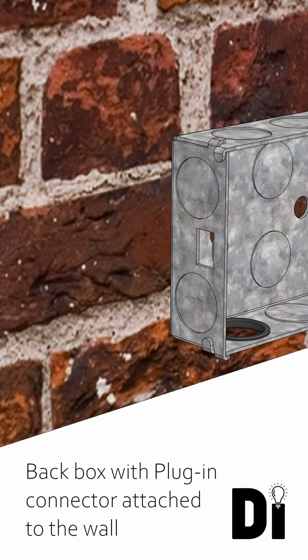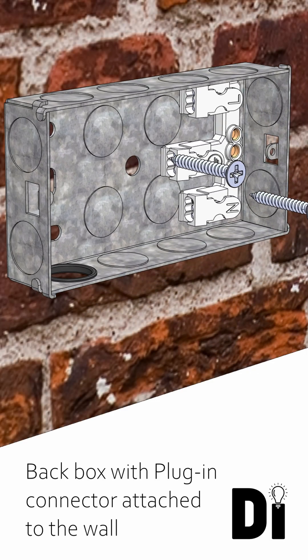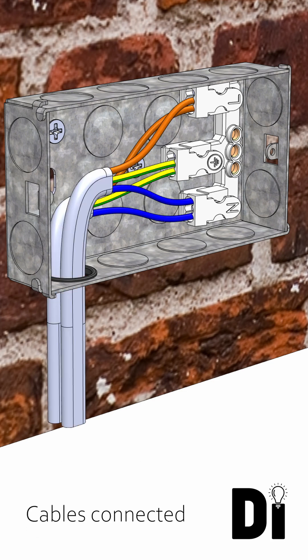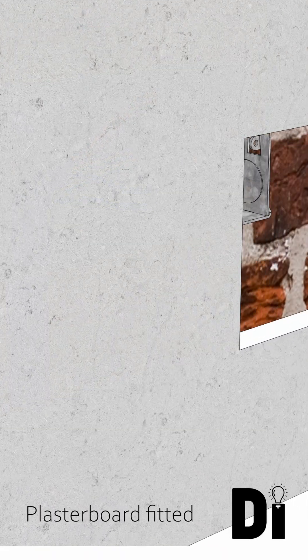This new design enables fixed wiring to terminate directly into the back box before wall finishes are applied. This allows for dead testing of the circuit cabling, including continuity of conductors and insulation resistance.